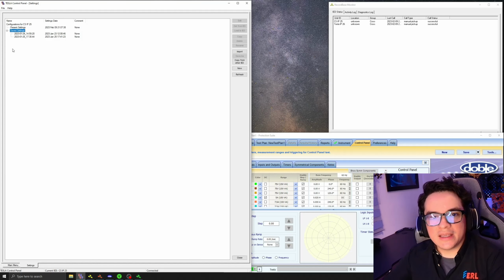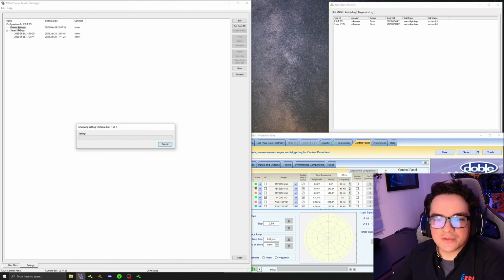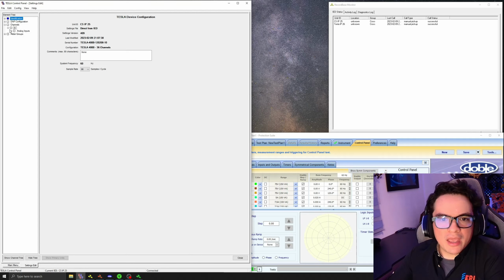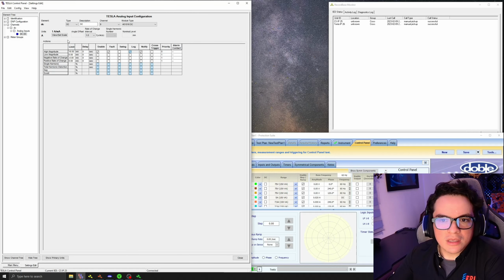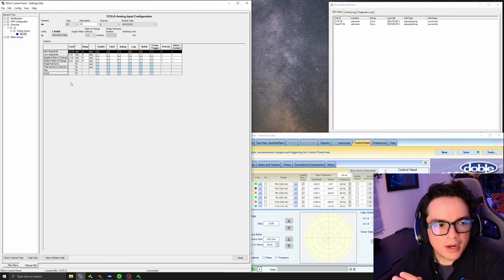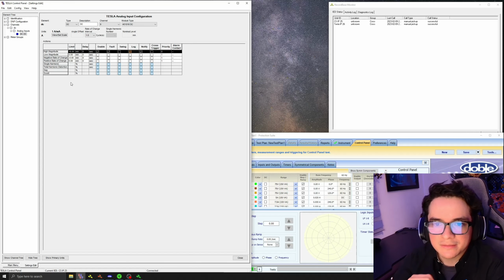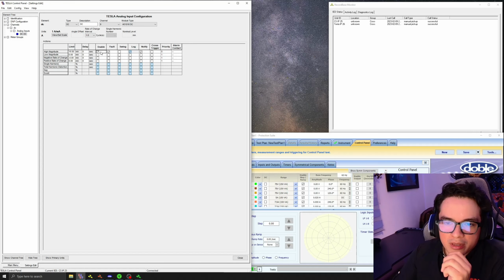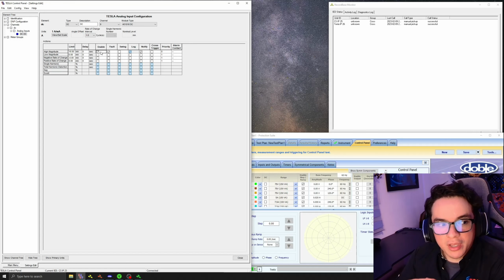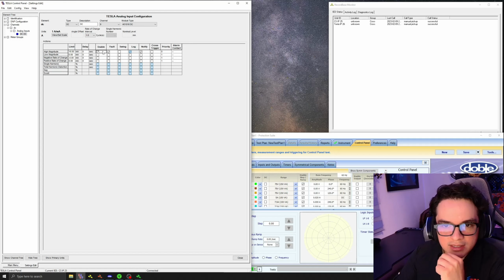Now we go into settings. Let's go into present settings to download the settings. And now I have here a DC channel. It's a DC channel on channel number 9. And I'm going to create a record using a high magnitude trigger of 16 milliamps. First, I have to enable the channel, of course. Well, no, the trigger of the channel, because this is channel number 9. So this is going to be the trigger of high magnitude and DC current.